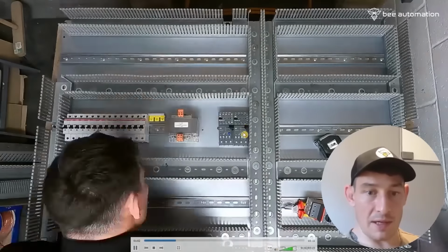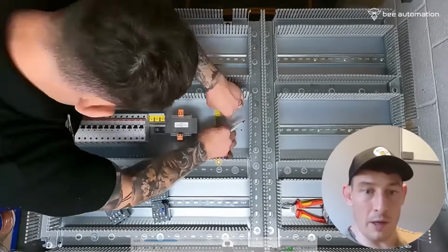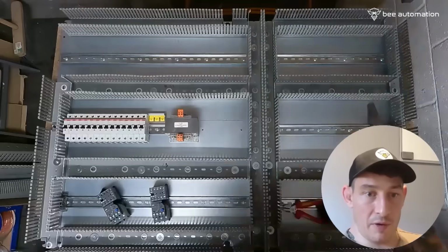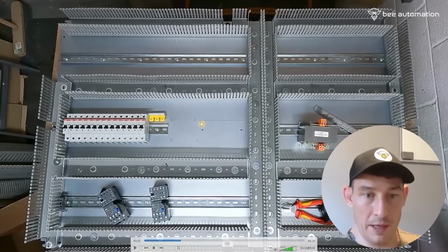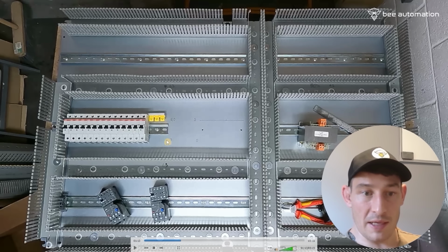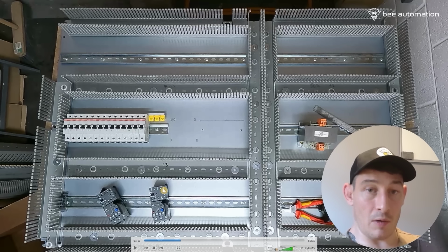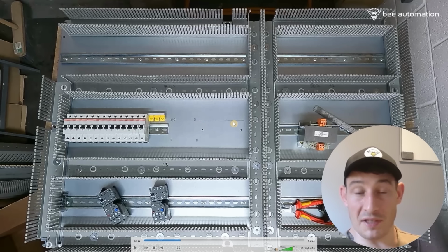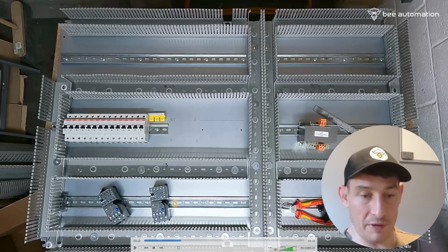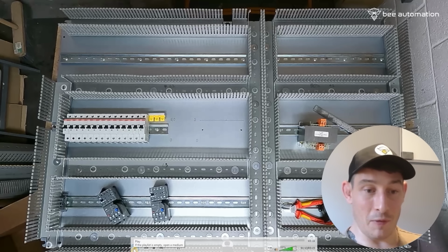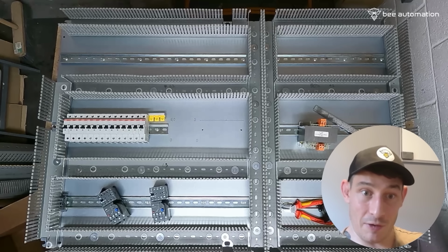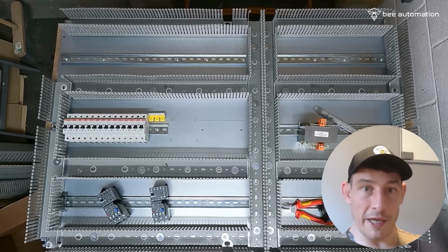Next thing is filling that gap with the contactors and overloads and the transformer. So just marking that out, getting those holes marked, and then drilling and fixing. You can see this center line for the din rail is higher than this din rail because these contactors actually sit on a din rail over here. And to have the combined contactor and overload central, we obviously need to move the din rail up. So that's just something to be wary of and considerate of if you're fixing components that have an add-on, to make sure they then sit centrally within the trunking spaces.